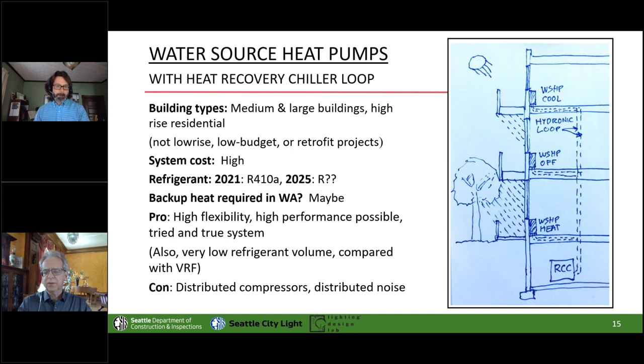Yeah, so Ben, there's obviously some refrigerant down in the heat recovery chiller. There's also some kind of water source heat pump. Yeah, but there's no field connections of refrigerant, so it's all done under factory conditions, and it's relatively small volumes because there's no long runs of piping. Right. And the alternative refrigerants like the CO2s that are very high pressure, that's really viable here when you get down to single equipment instead of VRF scaled refrigerant systems.